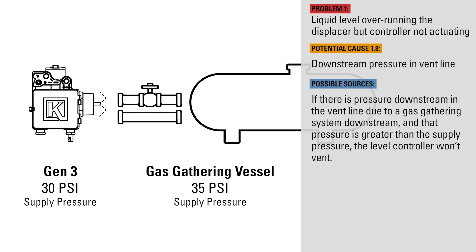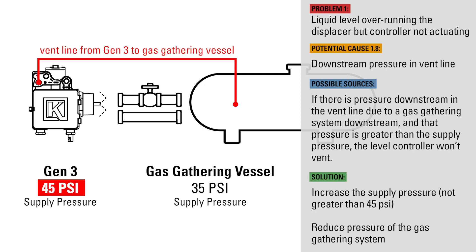If there's pressure downstream in the vent line due to a gas gathering system downstream, and that pressure is greater than the supply pressure, the level controller won't vent. Increase the supply pressure but no more than 45 psi, or reduce the downstream pressure of the gas gathering system.